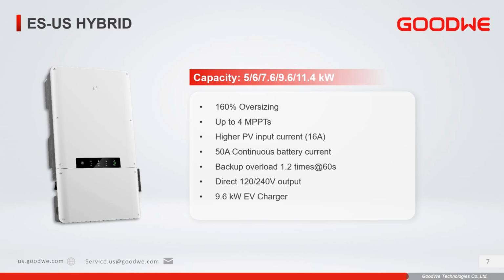The ESUS is one of our next generation residential storage inverters. This one is DC coupled. The smaller models have 2 MPPTs and the larger has 4 MPPTs. The inverters range from 5 kW to 11.4 kW. Oversizing is allowed in all of our inverters. However, the primary rule is that the string doesn't exceed the maximum voltage and short circuit current. In the storage family, we also have an AC coupled version, which is our SBP US. Both of these inverters are compatible with our GoodWe Lynx battery and the LG Prime battery.